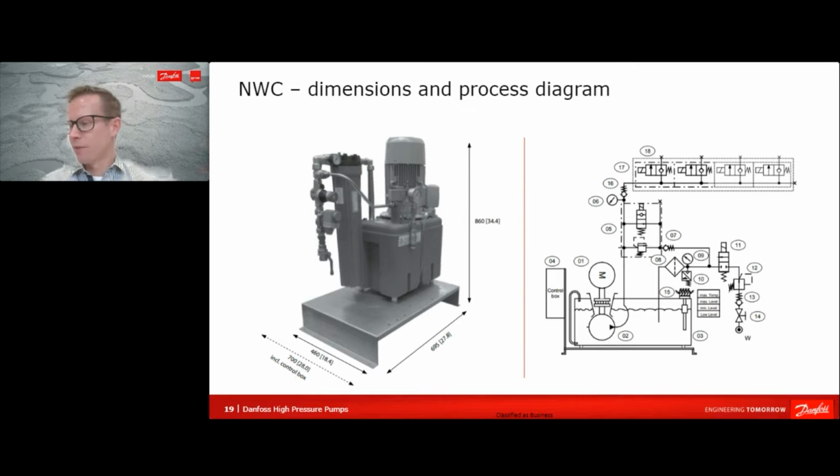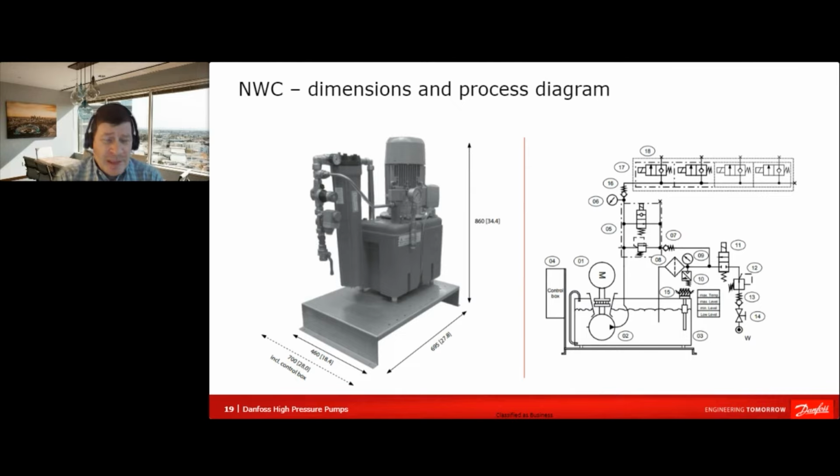Basically we recommend that, for example, if you have a saw line and you have a saw blade cooling application, there you have a different system, and for drying kilns you have other similar systems. So it's easy, for example in a service case, you have the same spares in all systems. But in drying kiln applications, you can serve several kilns with one unit. It depends on your automation, but if I remember right, 6 to 7 drying kilns is the maximum with 1 unit.